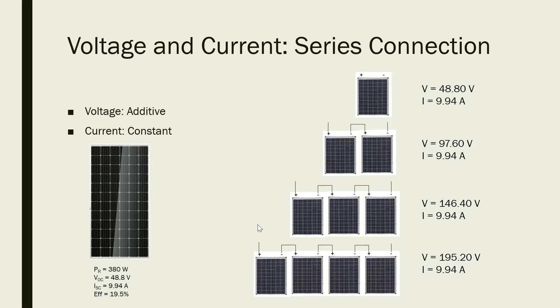And suppose we have four of these solar panels connected in series. This will give us an output voltage of 195.20 volts — that is 48.8 volts times 4 — and a current of 9.94 amperes.